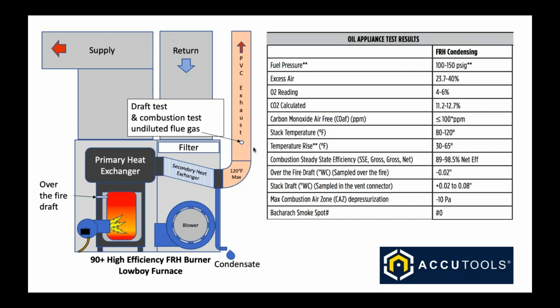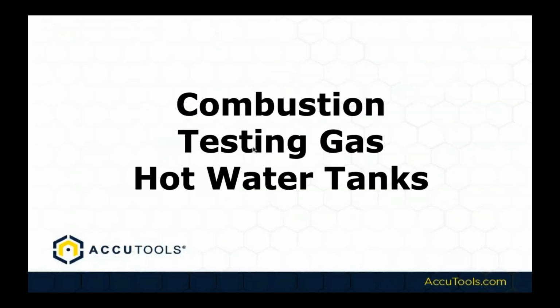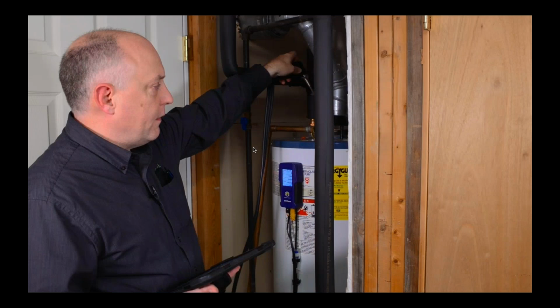And again, zero smoke. You have to pay really close attention to smoke on a condensing appliance because the secondary heat exchanger designs are very complex, and you don't want to clog that up with soot and smoke and unburned oil.